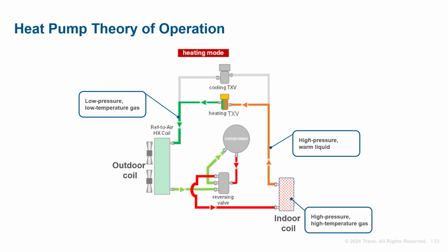As the gas makes its way through the outdoor coil, the outdoor TXV controller throttles the metering device to maintain a designed superheat. This device meters the proper amount of refrigerant and maintains the true suction pressure. The outdoor coil in this process is typically operating at temperatures 15 to 20 degrees below the outdoor temperature. During this process, the outdoor fans pull air through the outdoor coil and the heat energy in the ambient air is absorbed by the refrigerant. This is when the thermal transfer of heat moves from warmer to cooler. At this stage, the refrigeration cycle is complete and may begin again.